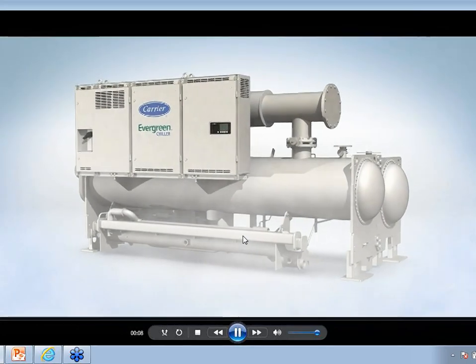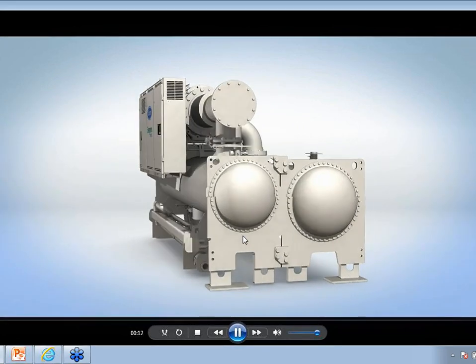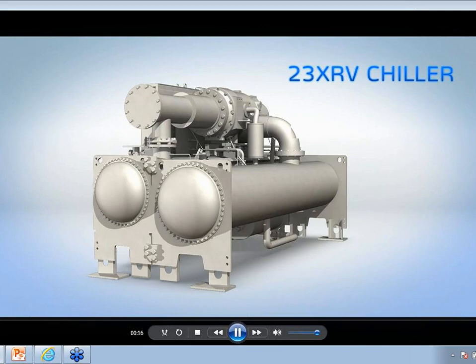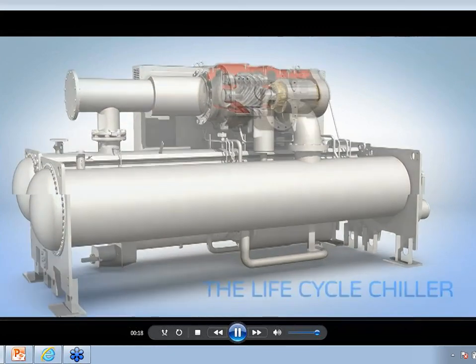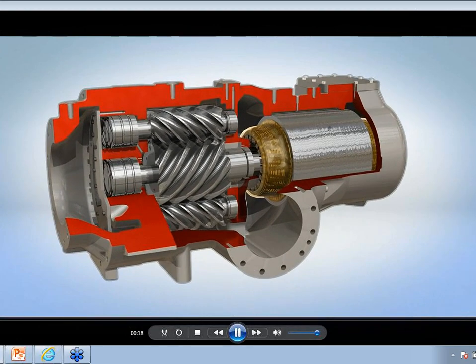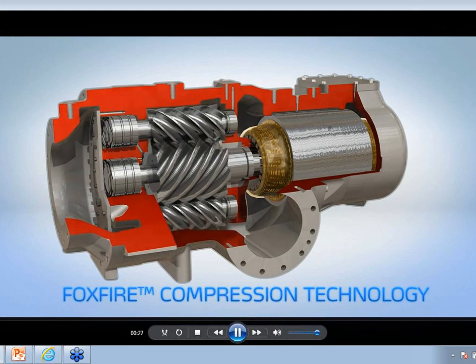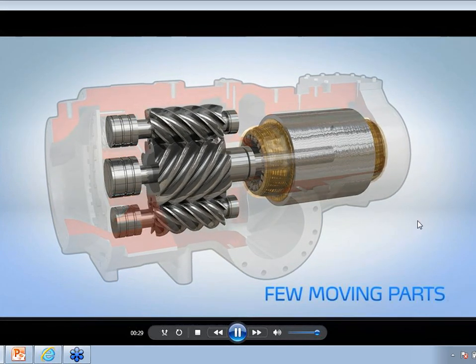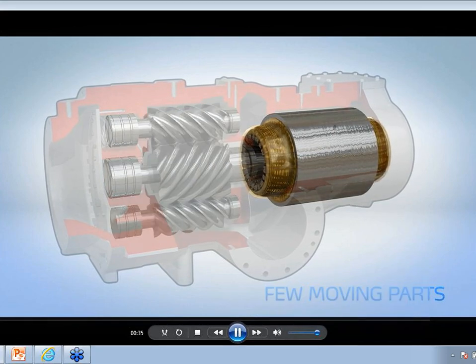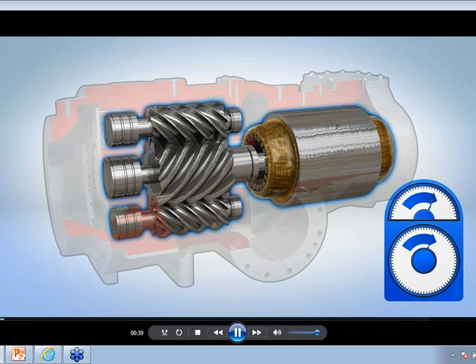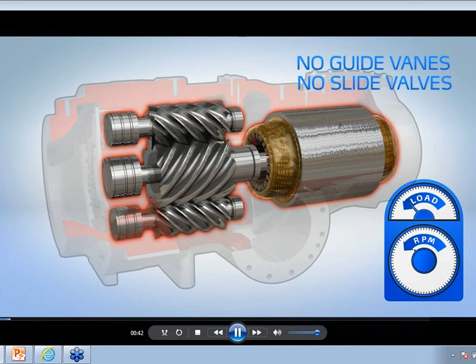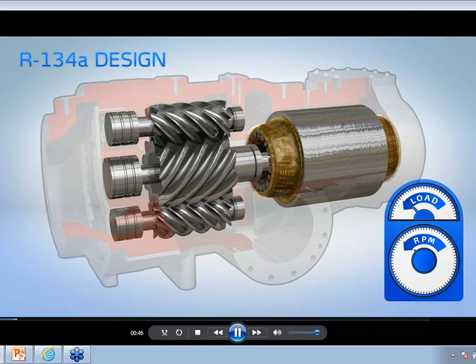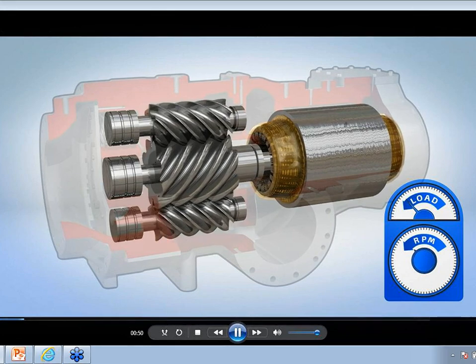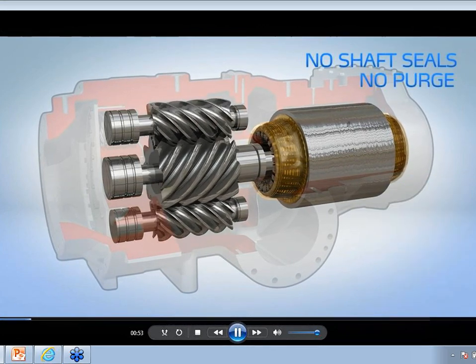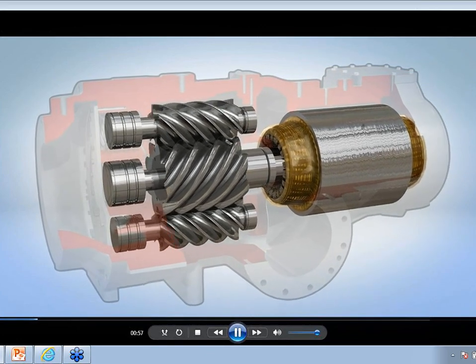The experts at Carrier have done it again with a surge-free chiller so tough. You may just forget how efficient it is. The Carrier 23XRV, the lifecycle chiller. The robust, dependable performance of 23XRV chillers stems from Carrier's advanced Foxfire compression technology. Brilliant in its simplicity, the only moving parts are the 3 screw rotors and variable speed electric motor. Capacity is controlled by simply regulating motor speed, completely eliminating the need for guide vanes or slide valves, while the semi-hermetic R134A design eliminates the potential refrigerant leaks and maintenance associated with shaft seals and purge units. Long bearing life is assured by working with the laws of physics instead of against them.